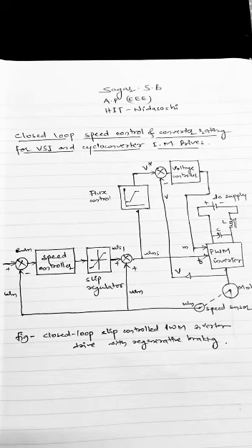Similarly, say there is a step decrease in speed command. It produces a negative speed error. The slip speed command is set at a maximum negative value now. The drive decelerates under regenerative braking, at the maximum permissible current and the maximum available braking torque, until the speed error is reduced to a smaller value. Now the operation shifts to motoring again, and the drive settles at a slip speed for which the motor torque equals the load torque.